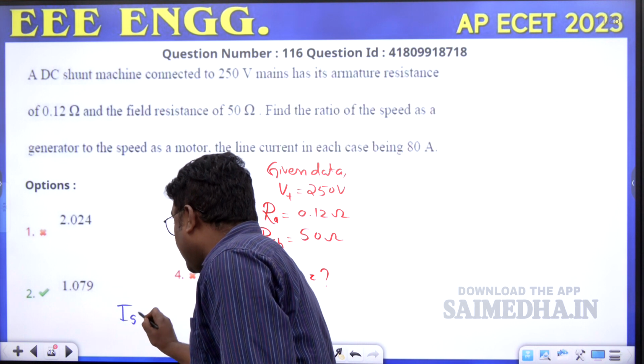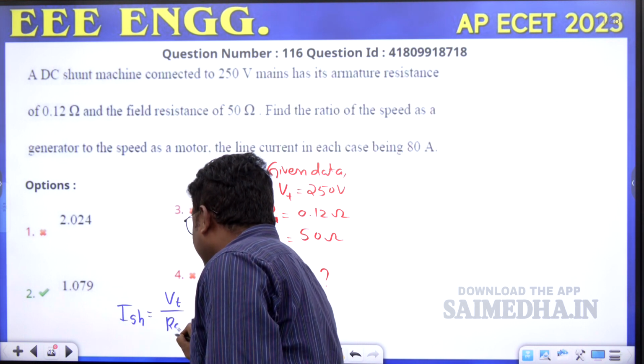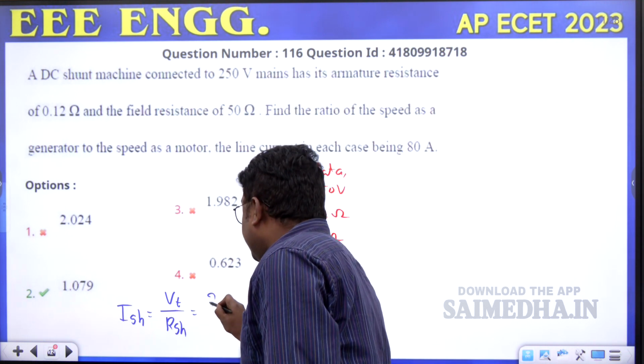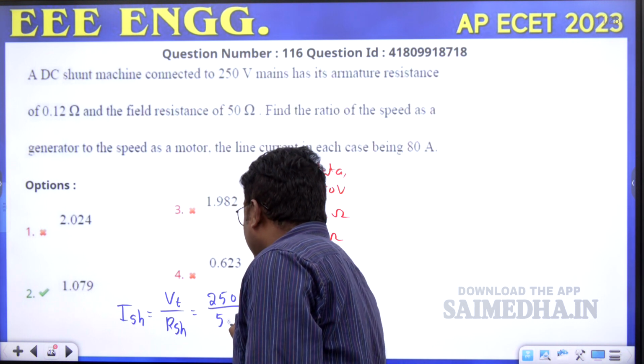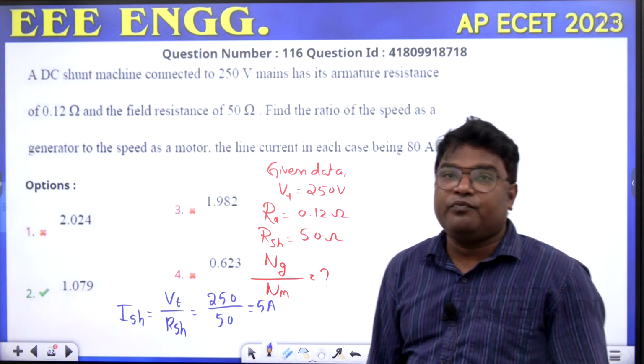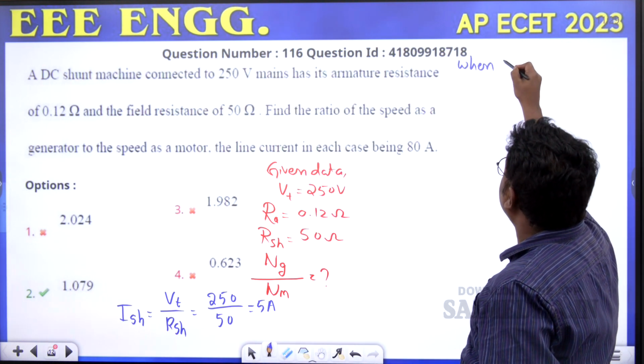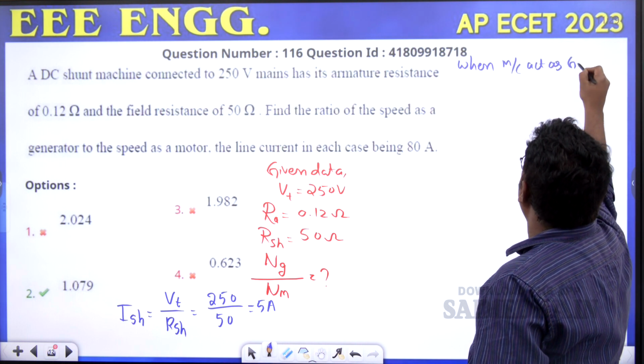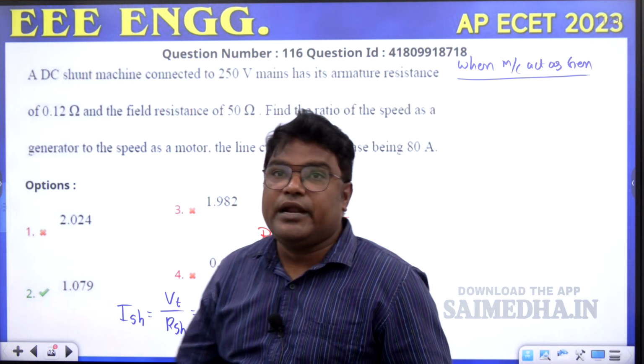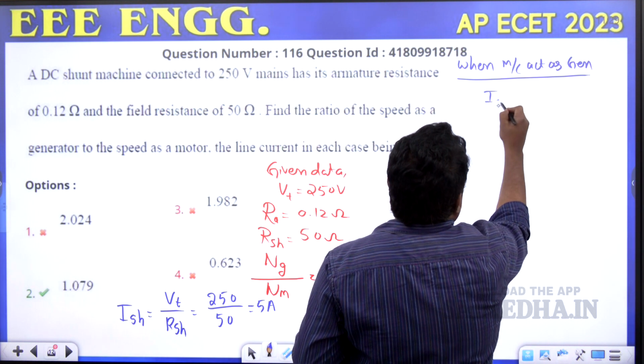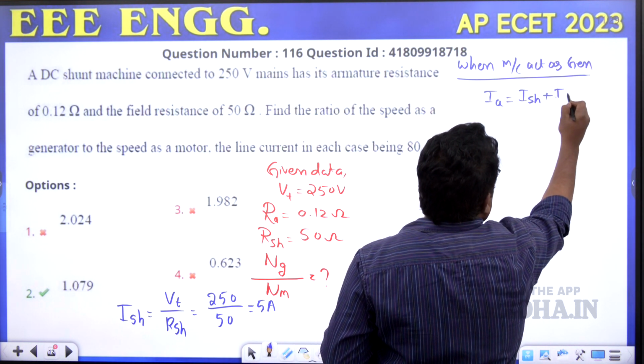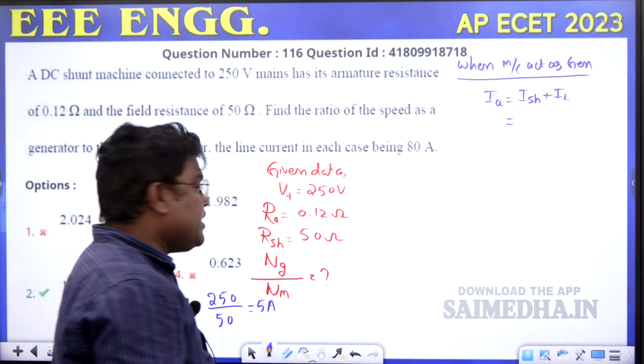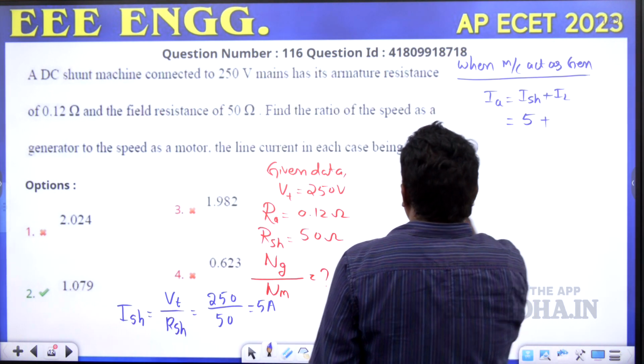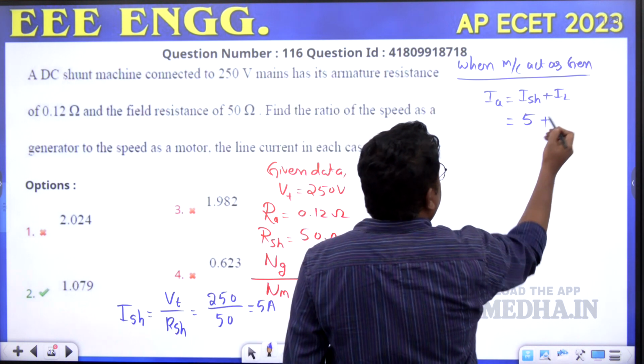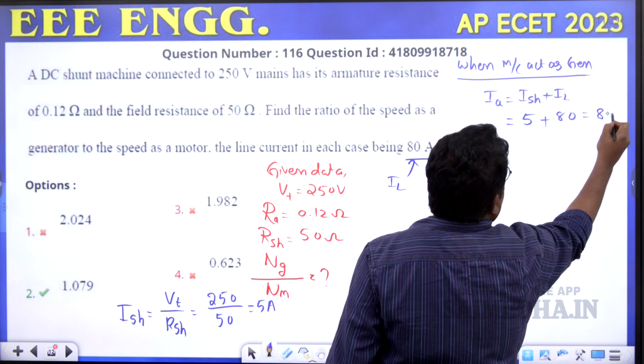Let us calculate the shunt field current first. ISH is equal to VT by RSH. The VT is 250 volts divided by 50, which is equal to 5 amps. This is the shunt field current. When the machine acts as a generator, the armature current IA is equal to ISH plus IL, the load current. ISH is equal to 5 amps and IL is equal to 80 amps, so IA is equal to 85 amps.